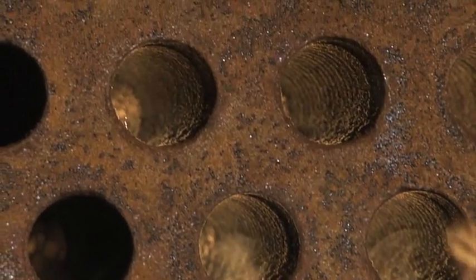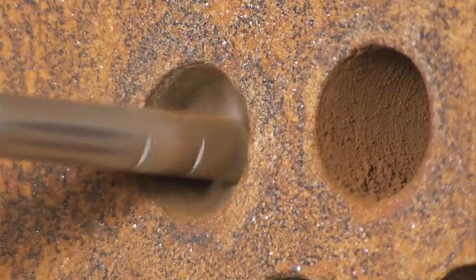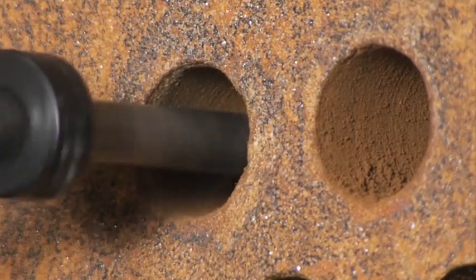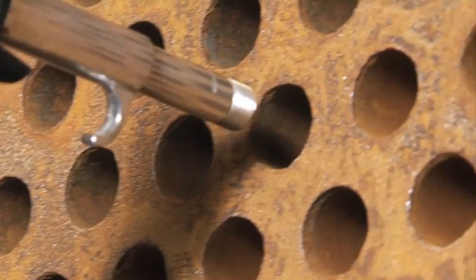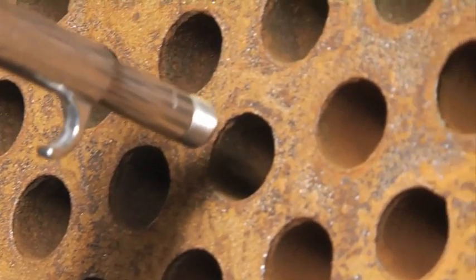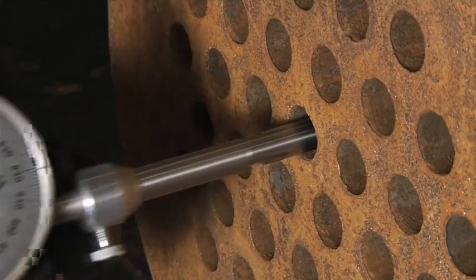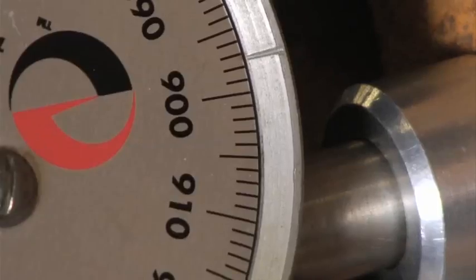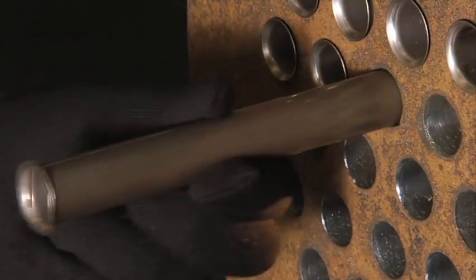Prior to installation, tubes are thoroughly cleaned. Tube ends are then wire brushed to the length of the shield and blown clear. Tube ID measurements are taken to determine expansion requirements and the shields are inserted into each tube end.